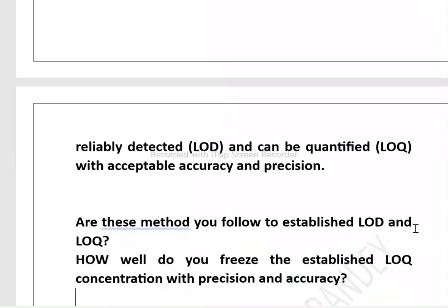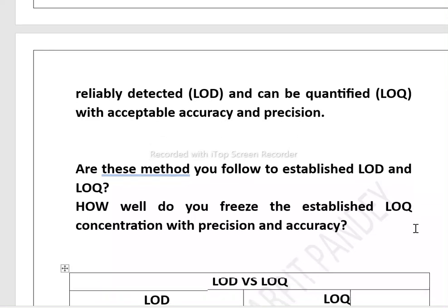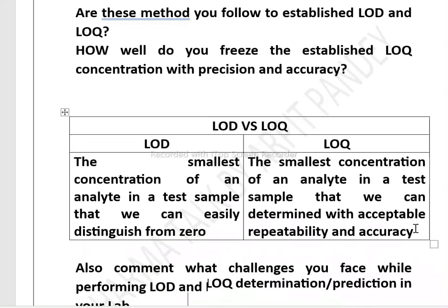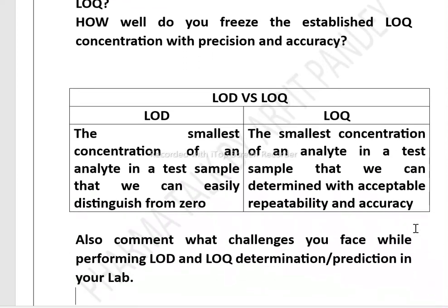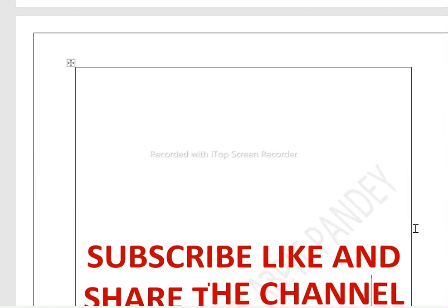I have some questions for you — please answer in the comments. Are these the methods you follow to establish LOD and LOQ precision in your lab? If yes, how well do you achieve the established LOQ concentration with precision and accuracy? The basic difference between LOD and LOQ: LOD is the smallest concentration of analyte in a test sample that we can distinguish from zero; LOQ is the smallest concentration of analyte that we can determine with acceptable repeatability and accuracy. Also comment on what challenges you face while performing LOD/LOQ determination in your lab.